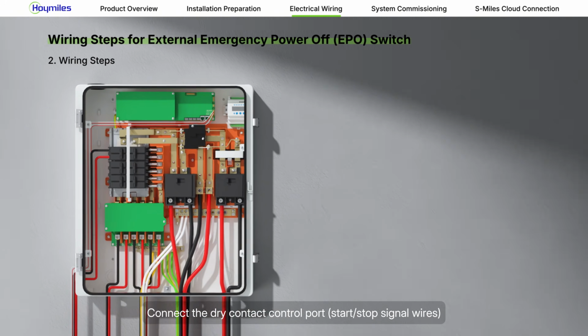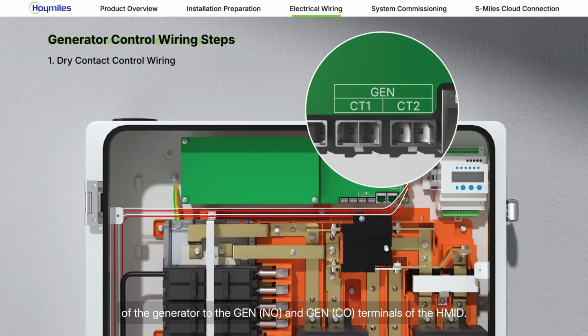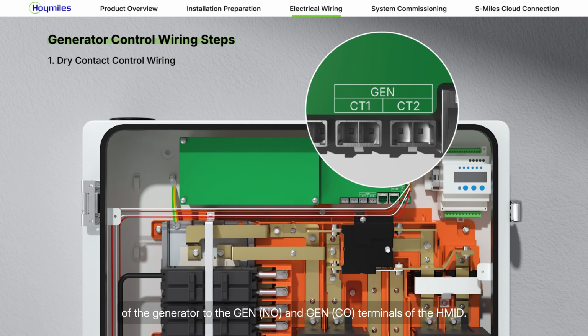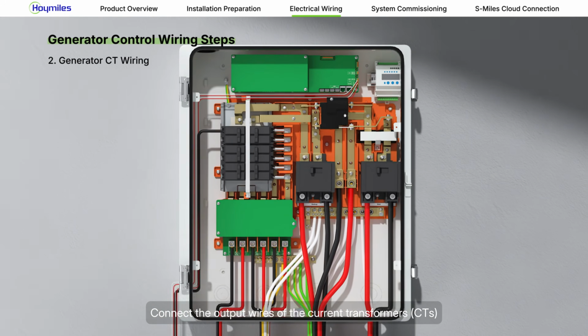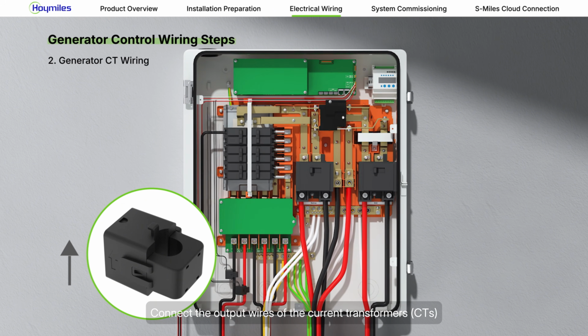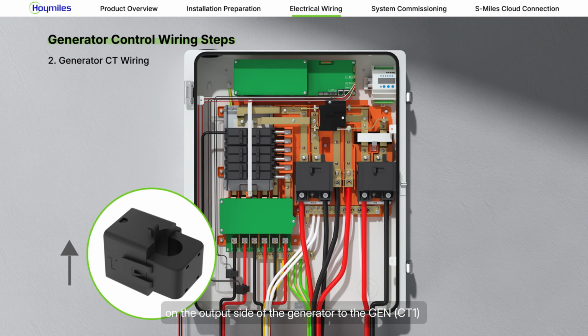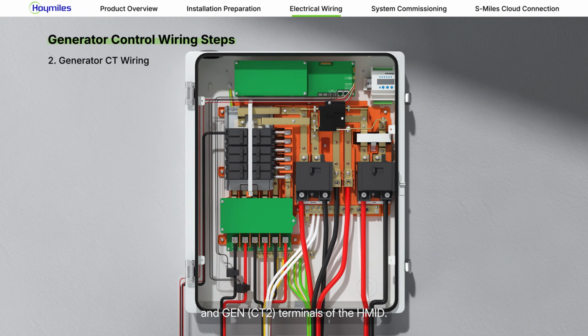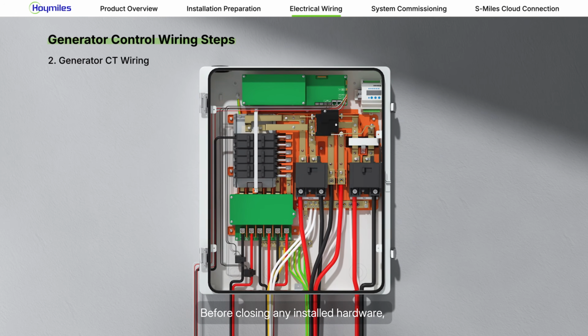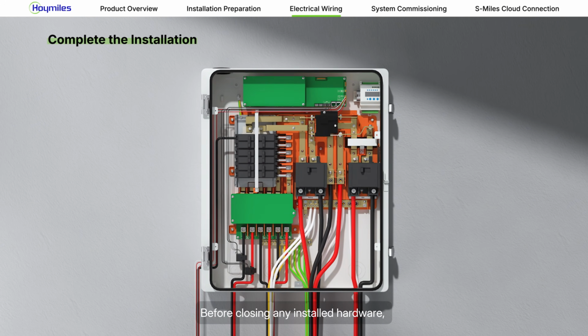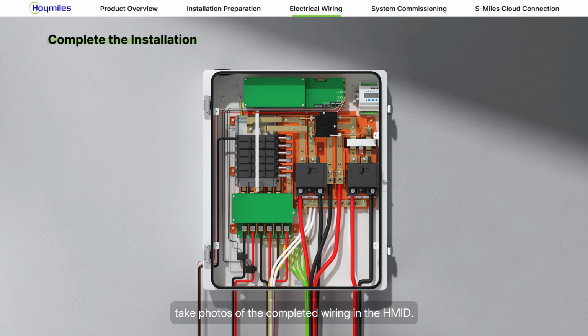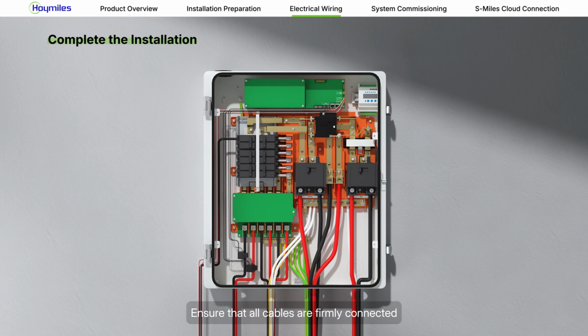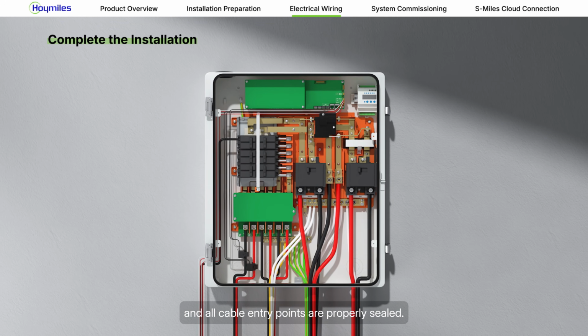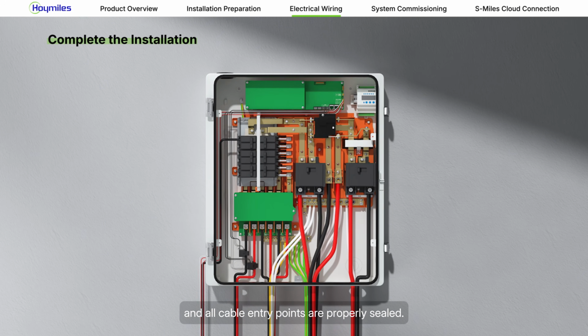Connect the dry contact control port of the generator to the GEN and GEN terminals of the HMID. Connect the output wires of the current transformers on the output side of the generator to the GEN and GEN terminals of the HMID. Before closing any installed hardware, take photos of the completed wiring in the HMID. Ensure that all cables are firmly connected and all cable entry points are properly sealed.